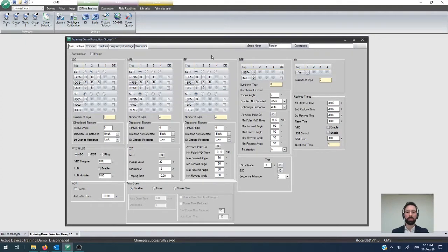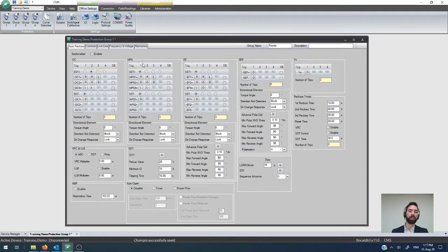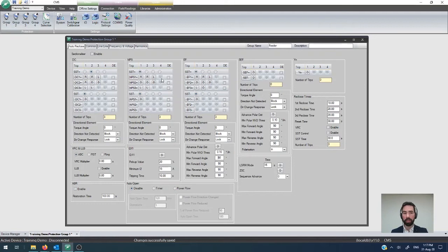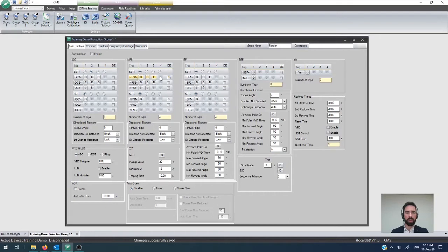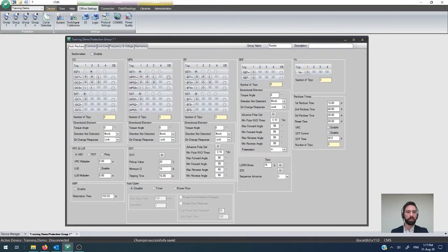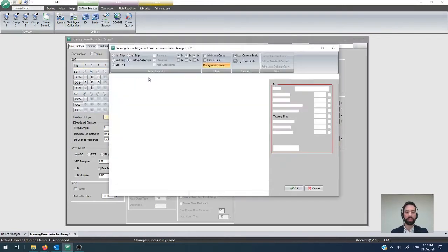For those of you that have watched our overcurrent video or our earth fault video, the configuration for negative phase sequence is pretty much the exact same thing. You have a reclose map that determines what you're going to do, tripping on the first, second, third, and fourth trip, up to as many as you'd like to have. Then your ability to either polarize that by making it a directional element or just to act on magnitude by itself, which is the default configuration. I'm just going to save that one there.